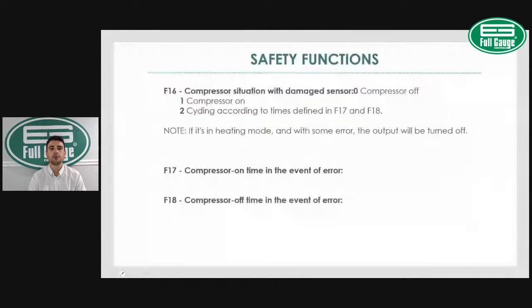So that will allow you to set, let's say, if my sensor fails, I might want my unit to run 10 minutes on and 5 minutes off. That way I can have cooling while the sensor is being replaced.